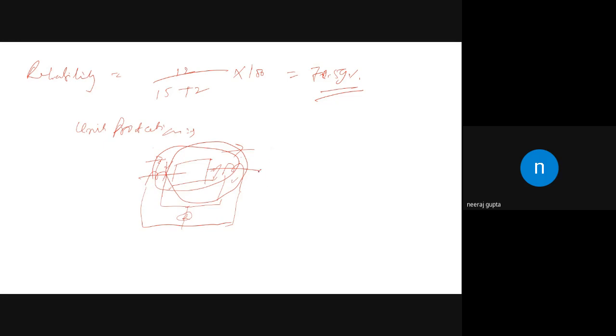Let us suppose we place the CT here, then the zone of the protection would be from here to here. Where we place the CT, the zone of protection would be from that. So this is known as the unit protection scheme, because we want to protect the whole of the unit. Many of the equipments in which the unit protection scheme is used are transformers, generators, induction machines, reactors in some cases, etc. So the unit protection scheme is intended to protect that particular unit.